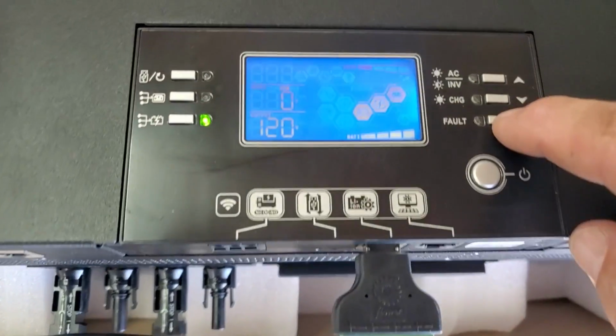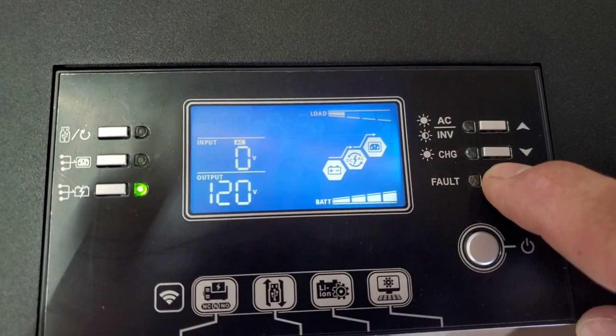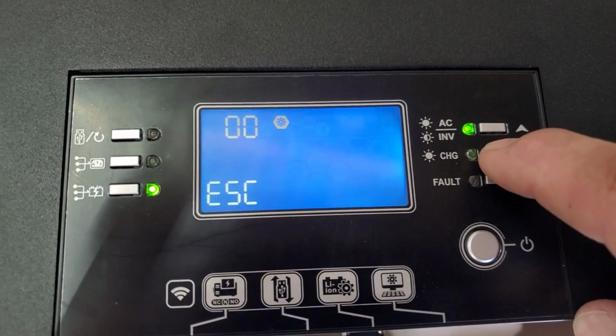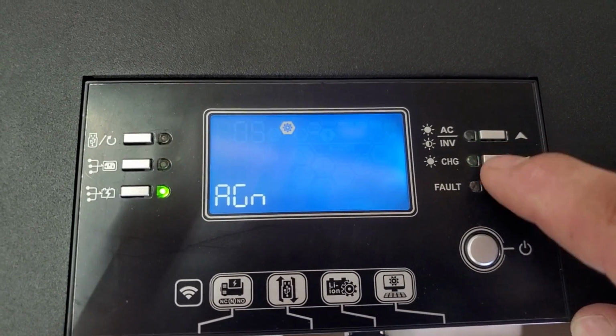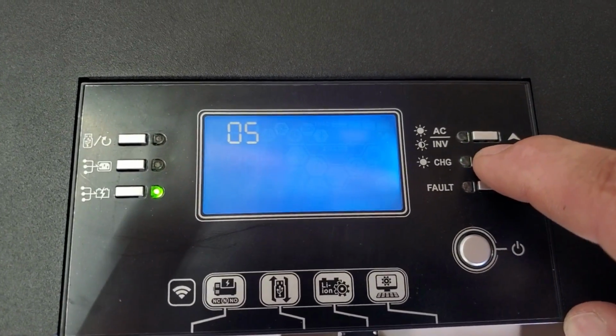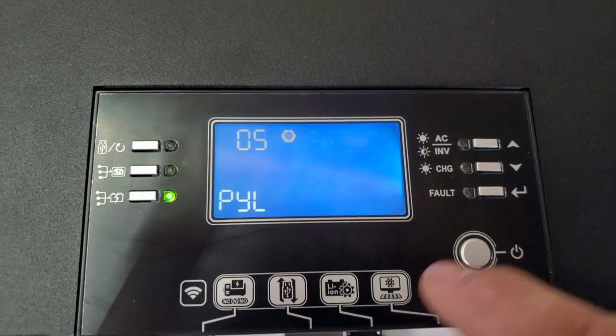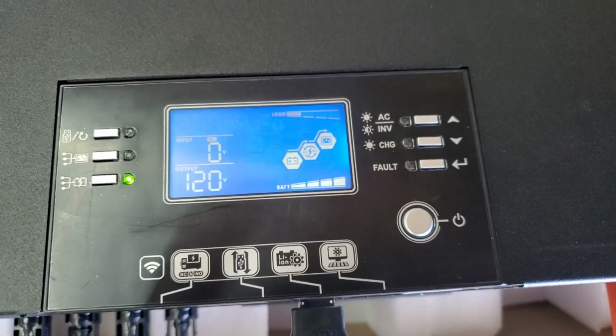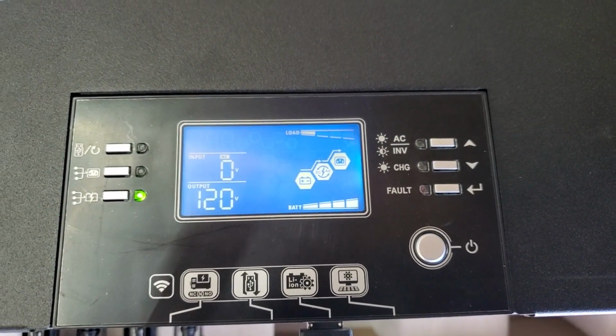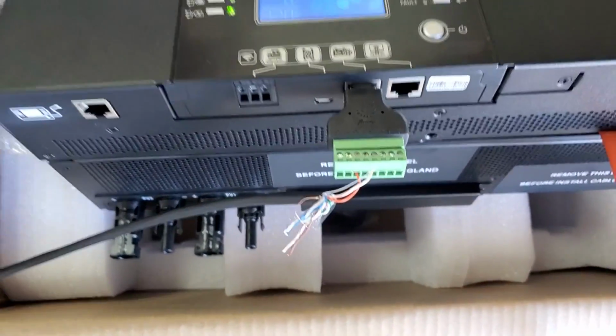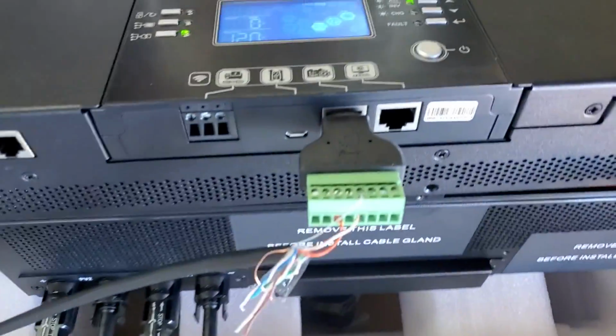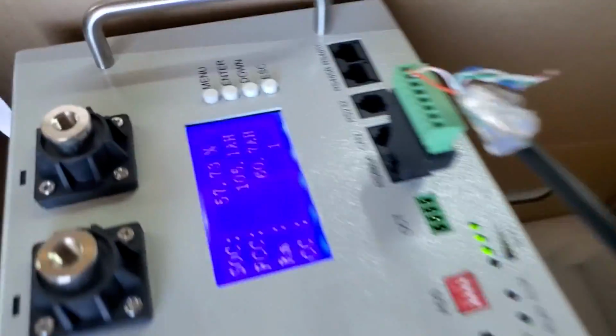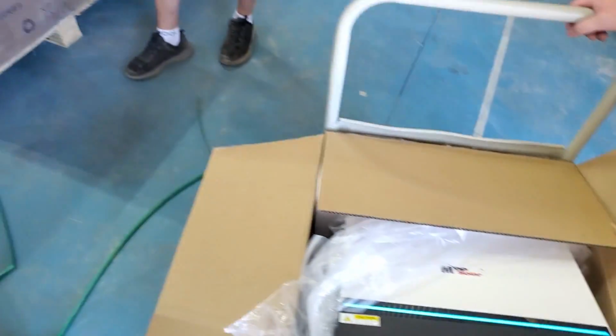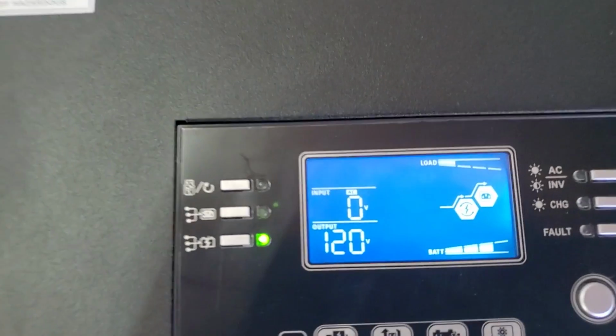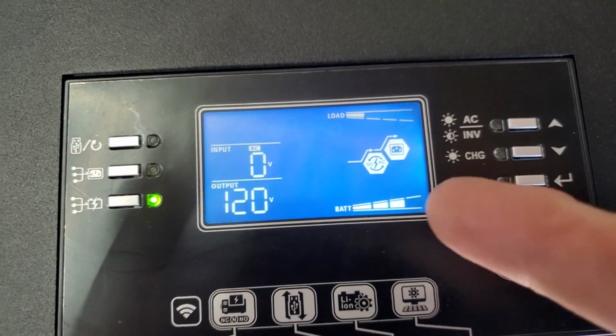Now we're going to set this inverter's battery type to PYL, and let's see what happens — we're going to see if the communication works. We've got that communication cable plugged into that port and into the RS485A port. And what do you know, it's communicating straight out of the box, no firmware update needed.